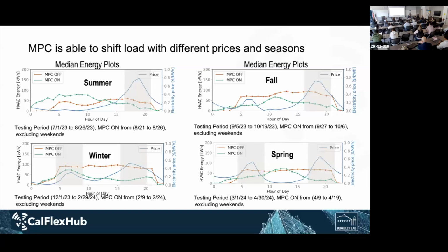And in particular, in these plots, you see the blue lines are the prices, so summer, fall, winter, spring, which can be quite different. In the summer, we have a big single peak at night. In the spring, we have two peaks, one in the morning and one in the evening. And then also the demand of the building is different. And in general, the MPC did a pretty good job at shifting the load.